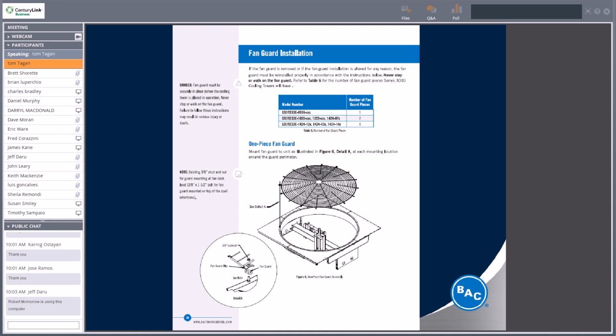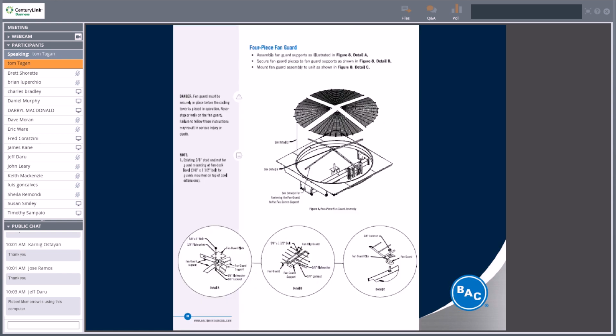Fan guard installation just shows you 1-piece, 2-piece, and 4-piece based on the size of your cooling tower. Generally, you're not going to need to take the fan guard off and put it back on, but if you do have to remove or replace a motor, sometimes it's easier to pull it out the top of the tower than to try to drop it down into the tower and pull it out the side, especially if you have an old tower that doesn't have internal access, or if you have multiple cells. Sometimes it's easier to drop it over the side of the installation versus trying to pull it through 3 or 4 different doors.